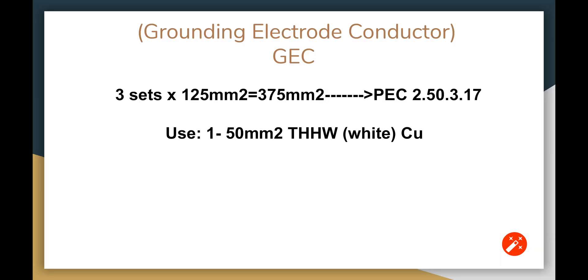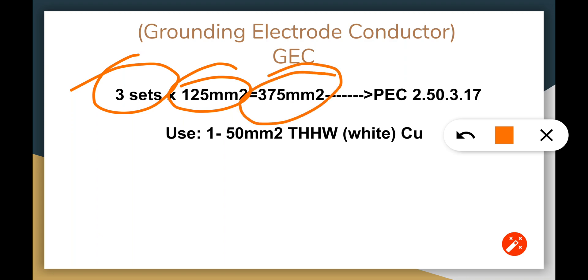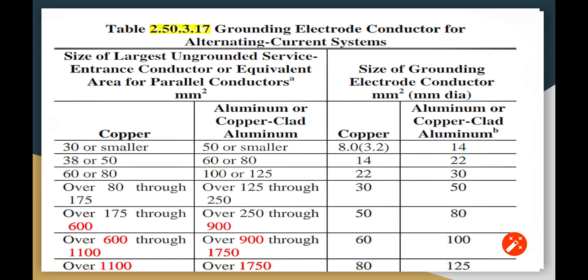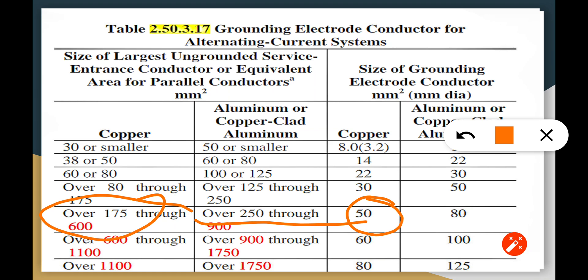The grounding electrode conductor is based on PEC 2.50.3.17. In three sets with three raceways, we have to multiply that by the 125 mm squared that we got earlier, and we shall get 375. So we're going to base this on PEC 2.50.3.17 and we shall get 50 mm squared. For 375, we get 50 mm squared, so we're at the minimum of 50 mm squared for our grounding in parallels.